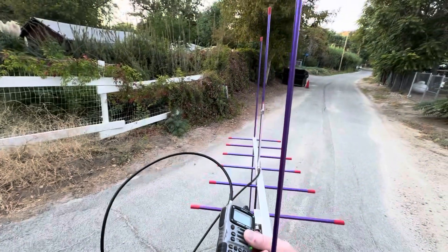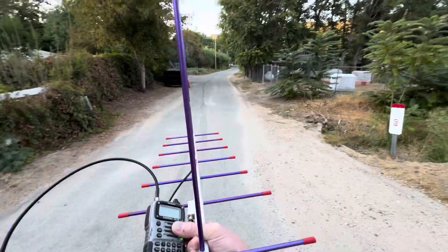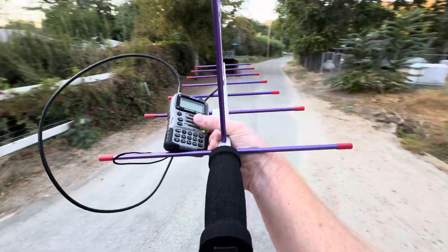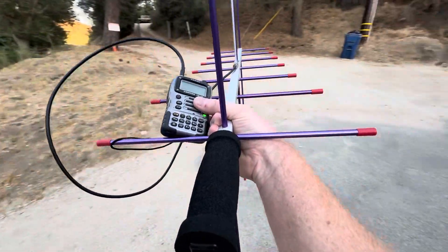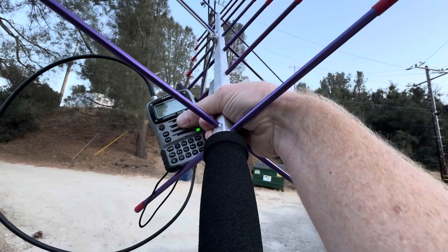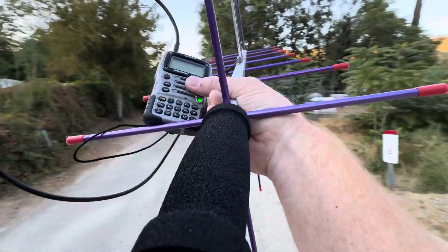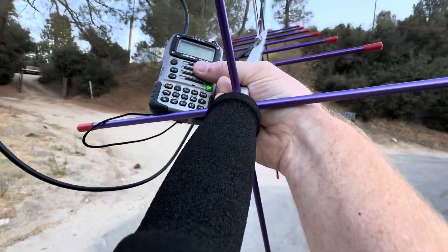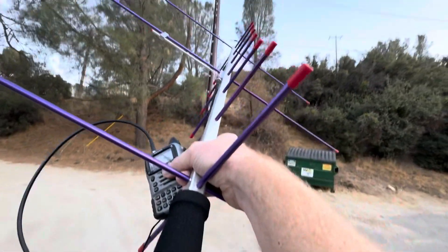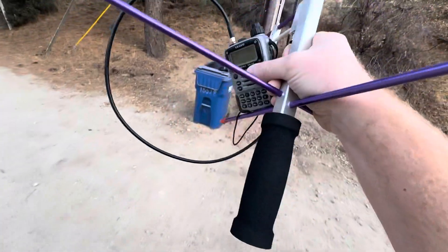Driving around the neighborhood, we got to a point where we found the strongest signal of interference. This is a directional antenna, so if I spin it around, it fades off and peaks right here at this pole. This is 144 megahertz noise.